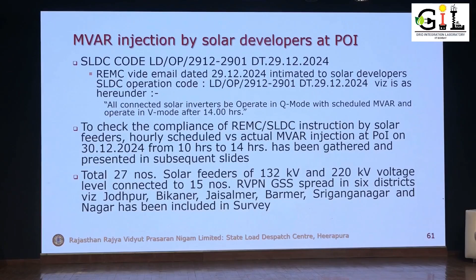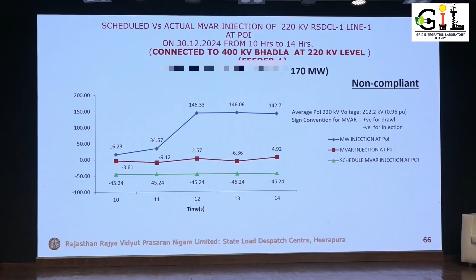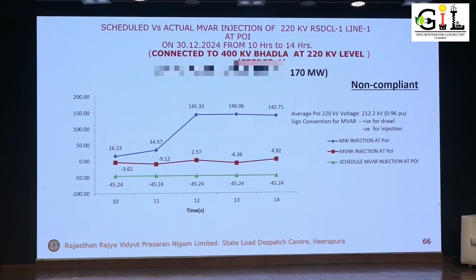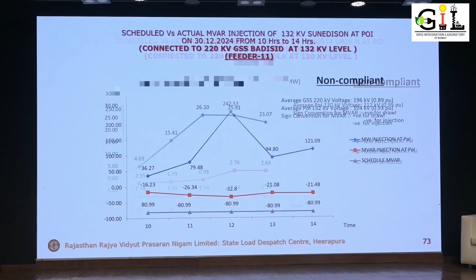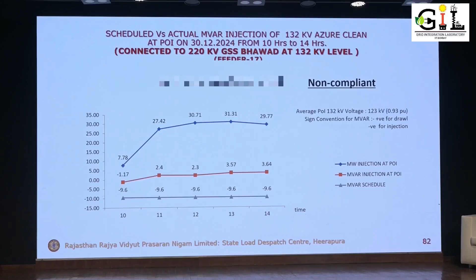We gave dispatch instructions for MVR, but they were not followed. So we conducted a survey, monitoring the substations and lines where bulk RE is connected. The compliance was not up to the mark. Against the 45 MVR that was to be injected at the POI, injection was hardly 3 MVR or 9 MVR, and sometimes they were even drawing 2 to 2.57 MVR. These are the results for different RE feeders. We recently called them and directed them to comply, but the compliance level is still not up to the mark.